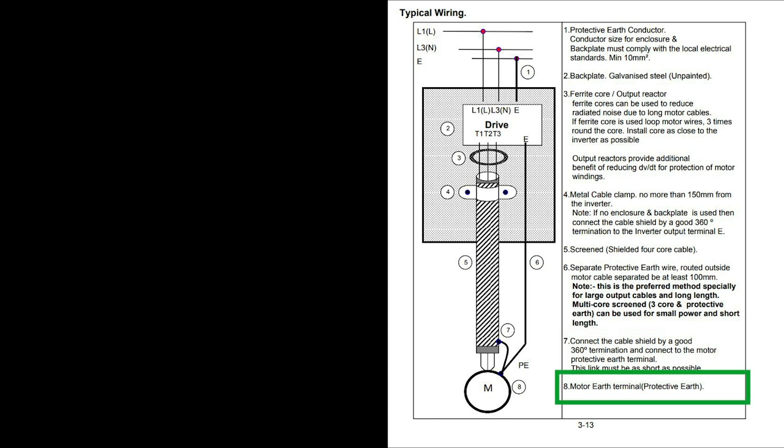The protective earth for the spindle housing goes back to the termination on the VFD and does not get looped around the ferrite core.